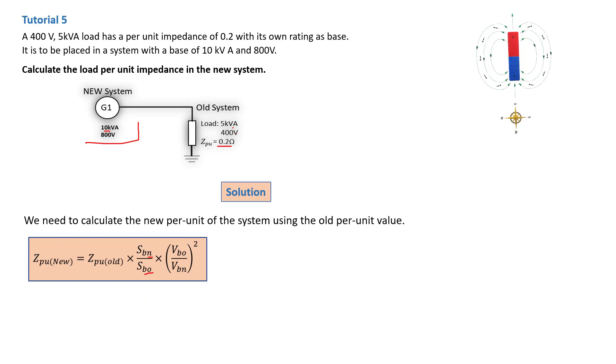...V base old, which is 400 volts of the old system on the load, over V base new, which is 800 volts of the new system. Basically, you just apply the general formula and figure out what quantities you have so you don't mix them up.